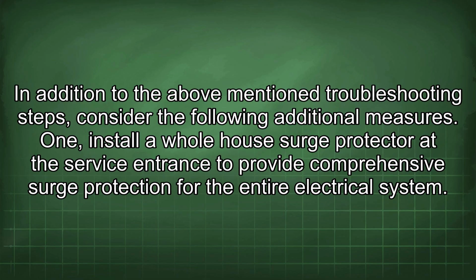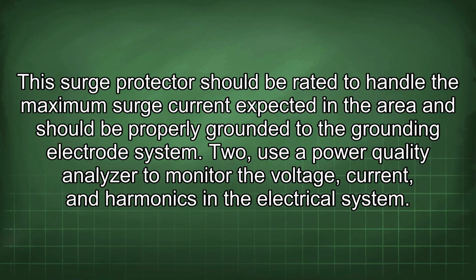In addition to the above-mentioned troubleshooting steps, consider the following additional measures. 1. Install a whole-house surge protector at the service entrance to provide comprehensive surge protection for the entire electrical system. This surge protector should be rated to handle the maximum surge current expected in the area and should be properly grounded to the grounding electrode system.